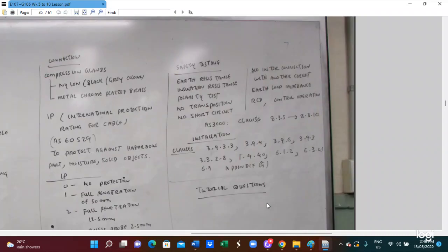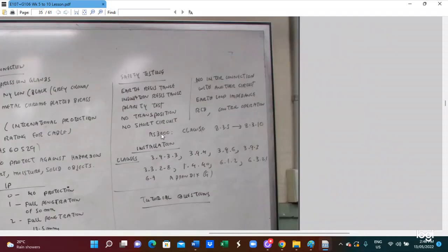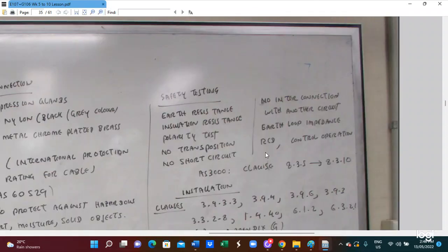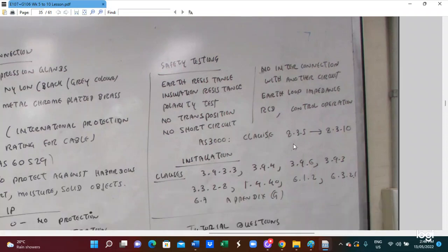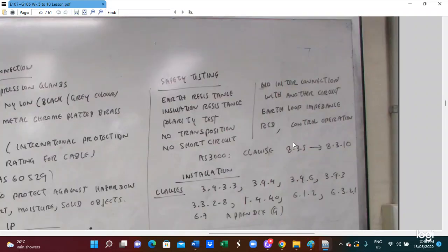And the safety issue is also important. Must have the insulation resistance test and polarity test. You have to do this appropriately. No transposition, no short circuit, no interconnection with another circuit, and also earth loop impedance and RCD operation.